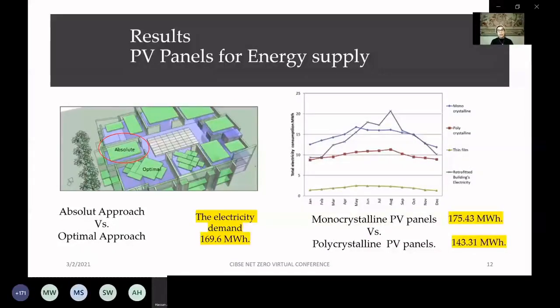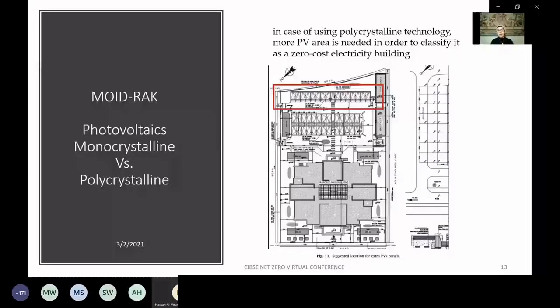To add more PV panels, a thorough analysis was conducted of the building site, and it was found that the orientation of the parking lot is very promising to provide a suitable area to add PV panels. The row highlighted in red shows that the shading for 16 cars could offer 220 square meters for PVs. By adding these PVs, this will transform our building into a net zero electricity building, even by using polycrystalline PV panels.